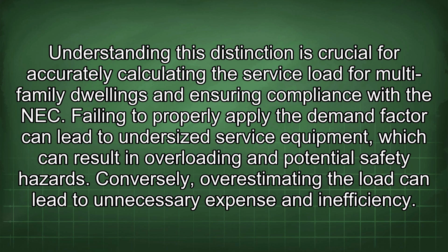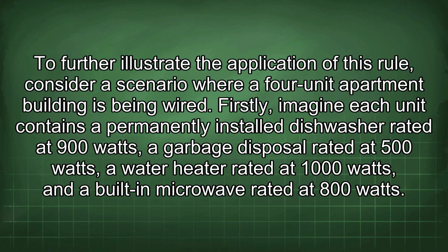Failing to properly apply the demand factor can lead to undersized service equipment, which can result in overloading and potential safety hazards. Conversely, overestimating the load can lead to unnecessary expense and inefficiency. To further illustrate the application of this rule, consider a scenario where a 4-unit apartment building is being wired.